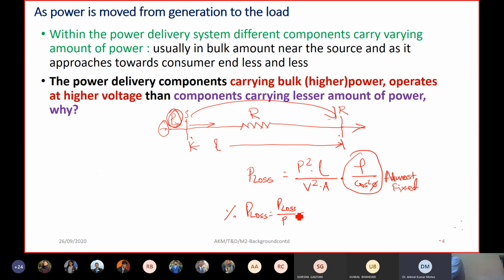So we can write that this percentage loss is proportional to PL by V squared into A into some constant. Very importantly, as I mentioned last time, not only does the total power loss vary proportional to P and L, the power and distance to be transmitted, but the percentage power loss itself varies proportional to the product of the power to be transmitted and distance.